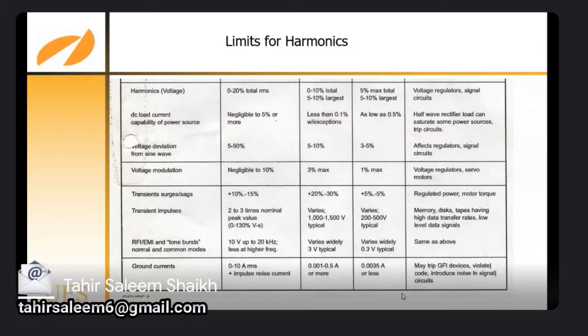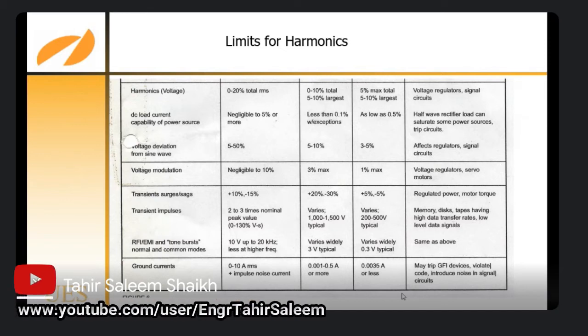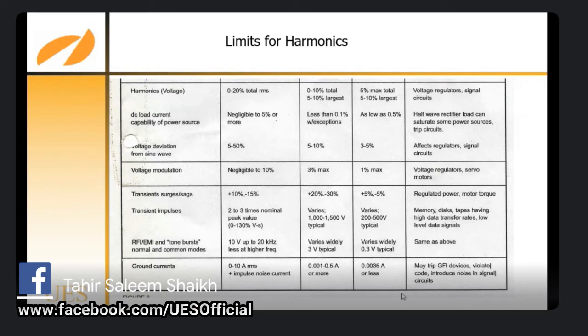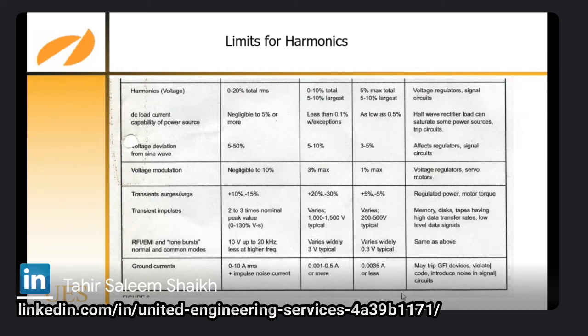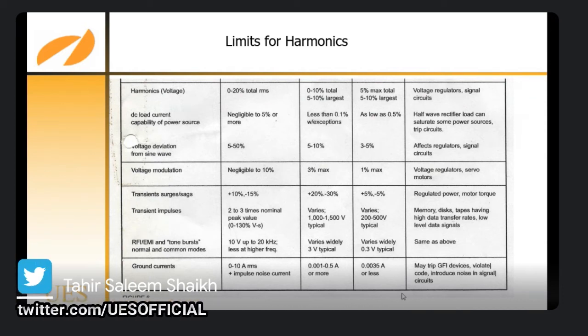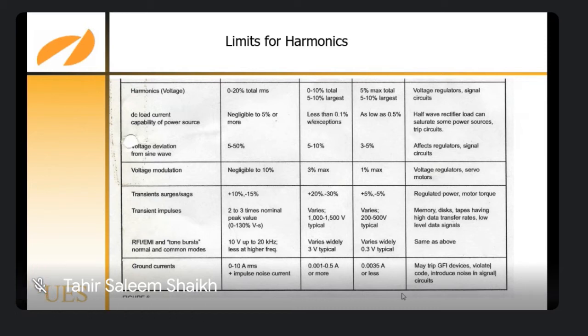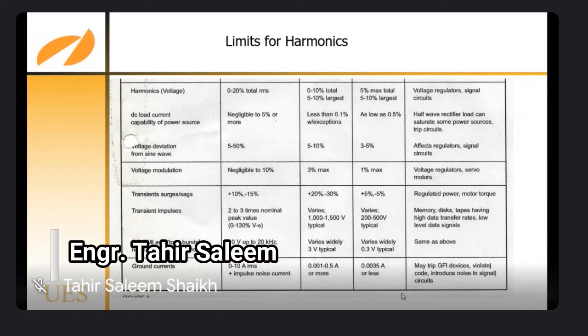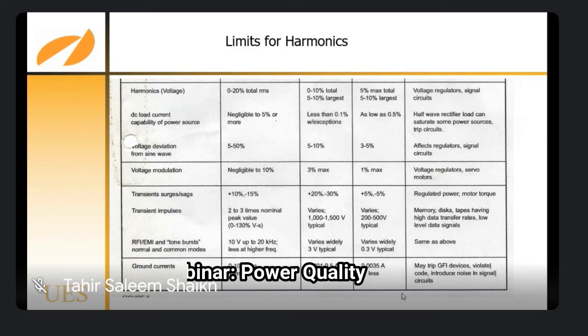Voltage modulation negligible to 10%, 3%, and 1%. Transient surges plus 10% minus 15%, plus 20% minus 30%, normal load of plus 5 plus minus 5%. EMI ground current should be 0 to 10 ampere, 0.001 to 0.5 ampere, this is leakage current, or more, or 0.0035 ampere or less. In general condition, the leakage current is normally 5 milliamps, but for the hospitals and other places, it is less than 1 milliamp.